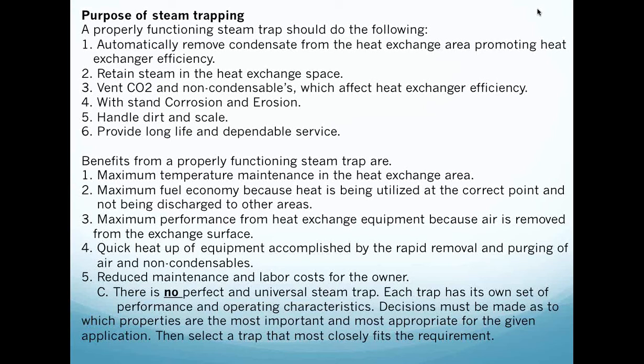If you do these things, and if you pick the correct technology and you oversee these as guardians, you will end up getting maximum temperature maintenance and efficiency, maximum fuel economy, maximum performance out of the heat exchange equipment. You will end up with quick heat up of your equipment because you will remove the air and the non-condensables, and at that point you will have the ability to completely fill that space up with steam. You will end up with reduced maintenance and labor cost.